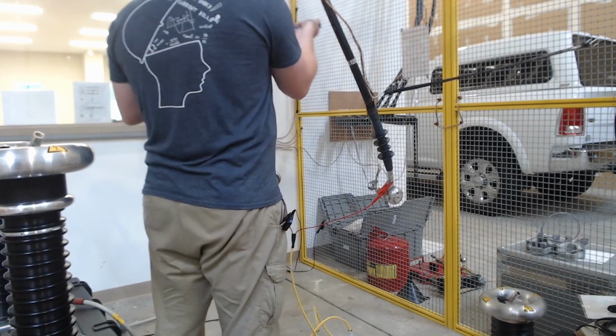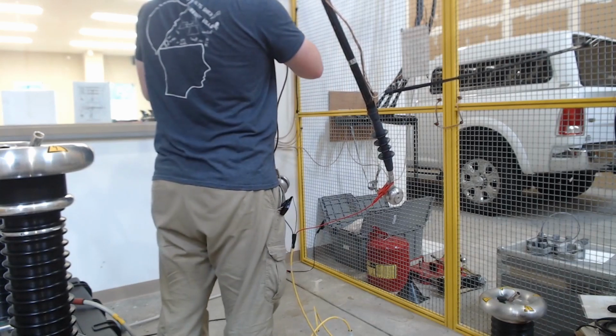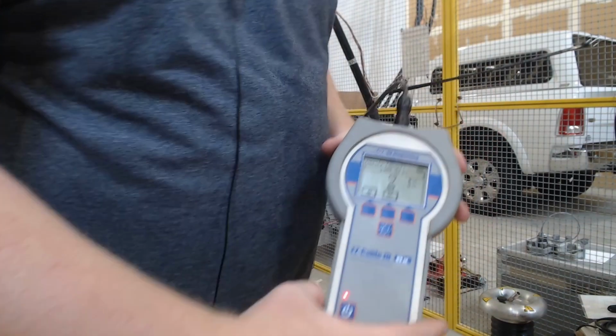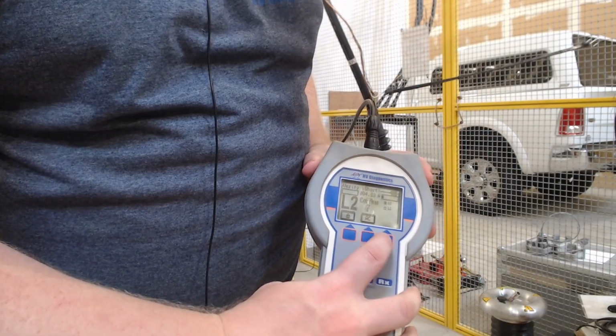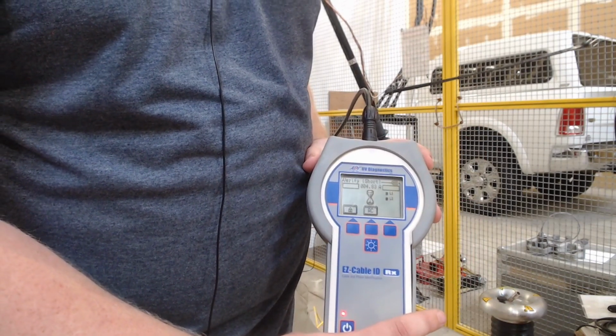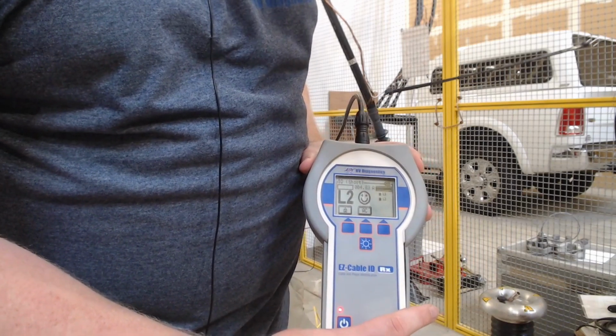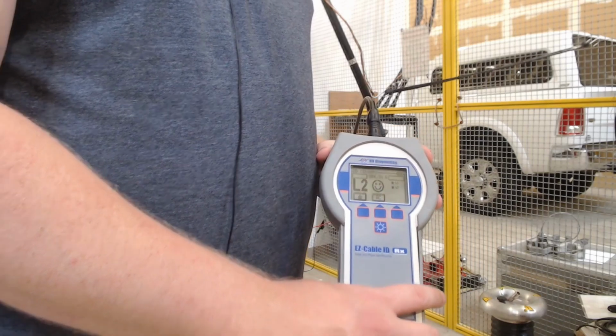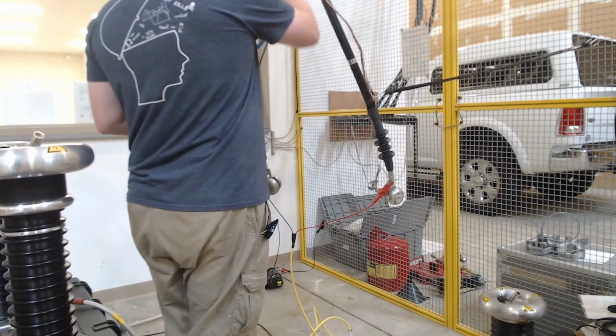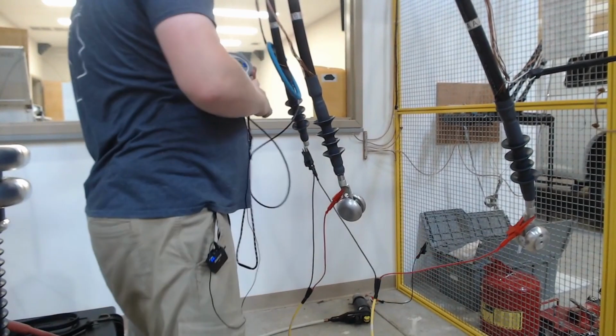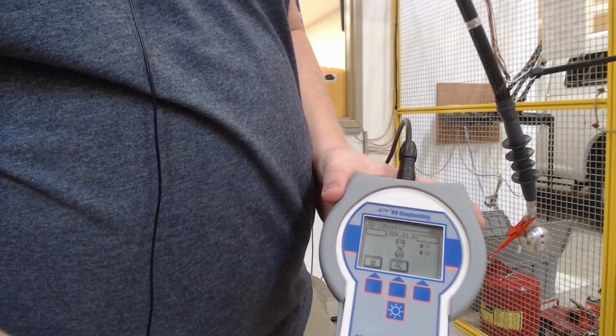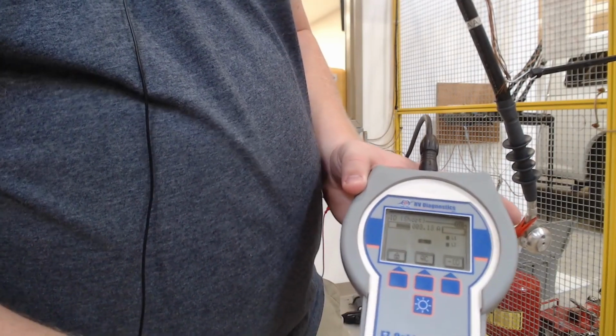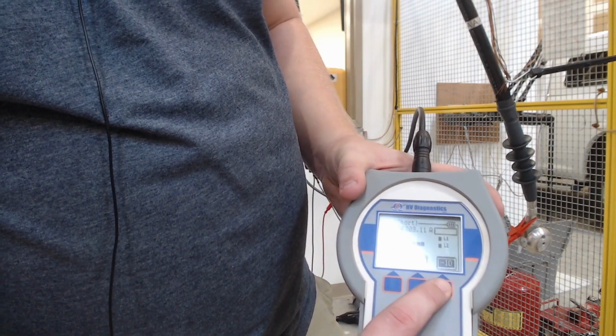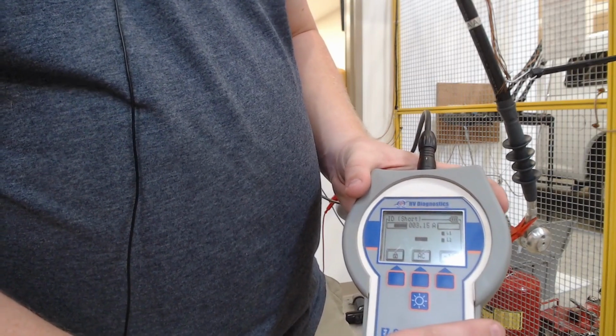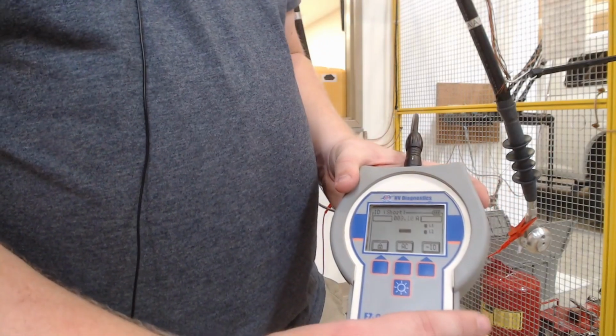Now we're going to move over to our B phase calibration. So it says L2 confirm, we are on L2. It's going to reread again. Should give us an L2 with a check mark, or L2 with a smiley face. So it is happy. So our calibration phase is done. If we want to verify on our third phase that our return is good, we'll move over to our C phase. And we should see a negative. There we go, we see our negative. So if we hit ID, we should see L1, and hit ID again, we see L2. So we have now confirmed that our return is in fact good, and we're getting all of our unique signals returned to us. And that is the calibration of the direct method.